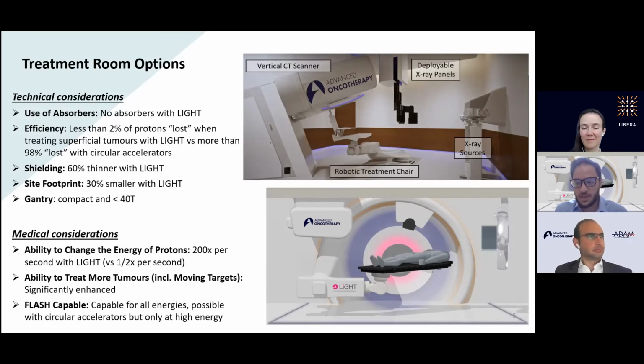So a couple of points that I just wanted to mention while we're on this slide. Light is a fully electronically controlled accelerator. There are no absorbers. The other important factor is that our beam losses along the accelerator are incredibly small, which makes the proton bunches that come out after the high energy beam transfer in the treatment room quite pure. As a consequence of a linear accelerator, with no moving parts or absorbers or mechanical parts, there is very little beam loss along the accelerating line, requiring even less shielding and ultimately vastly reducing the site footprint.